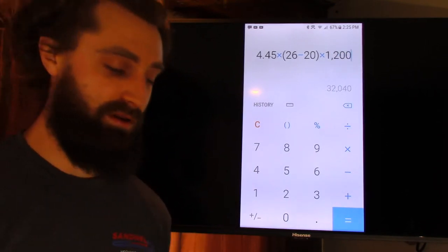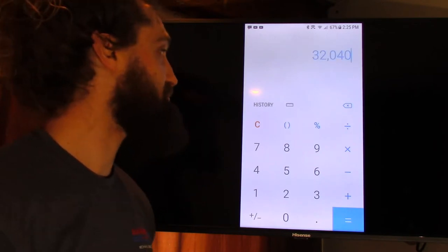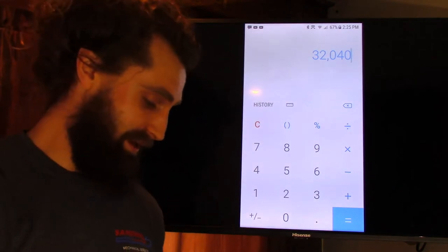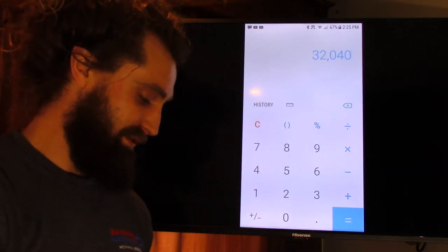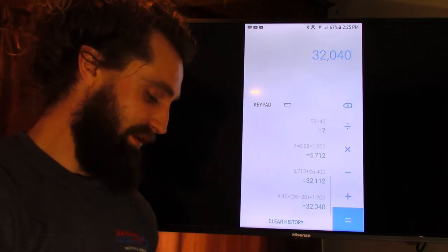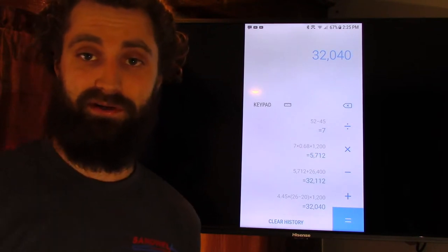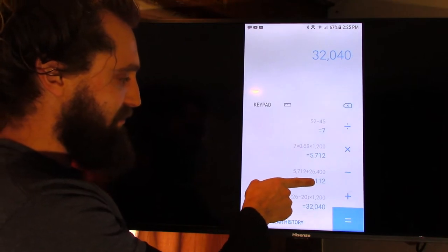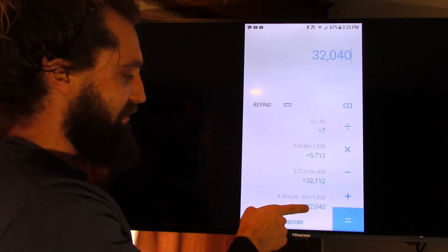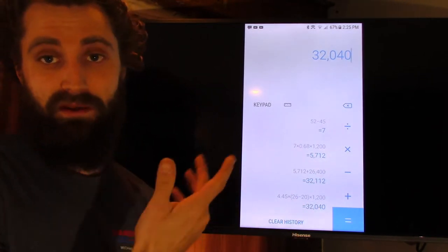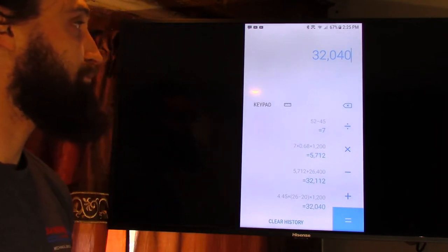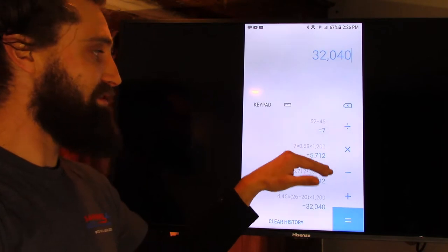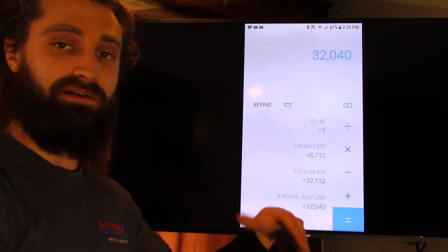Then we're going to multiply that times our CFM that we recorded, and you can see here that it comes out to 32,040, which actually I'm surprised it's that close. I'm only off by less than 100 BTU. So, yeah, I got 32,112, 32,040. So that's pretty good. But you can see this is a lot quicker. You're not having to add your sensibles and your latents together.